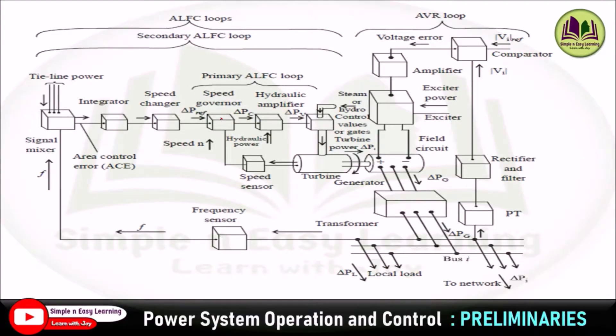If the differential speed is high, the control valve starts closing so that the speed of steam flow is reduced, thereby reducing the speed of the turbine as well. This control of speed in turn controls the frequency, since speed is directly proportional to frequency. In this primary ALFC loop, the speed of operation is very fast — it occurs in one to several seconds. Thus, to maintain a megawatt balance, this primary loop performs frequency control, also called speed control.